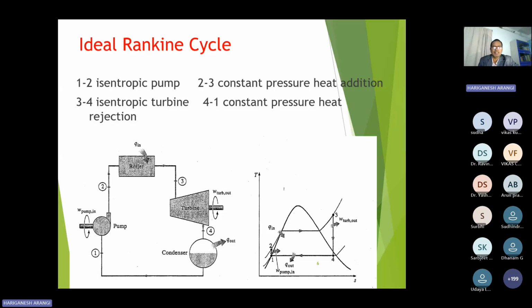The steam turbine operates on the Rankine cycle. Process 1 to 2 is the isentropic pump process. The pump takes water from the water storage tank, which is DM water. That pump takes the low pressure water and increases the pressure to around 90 bar up to 250 bar, depending on the power plant capacity. That high pressure water enters the boiler, where the heat exchange takes place. That pressure will be constant.